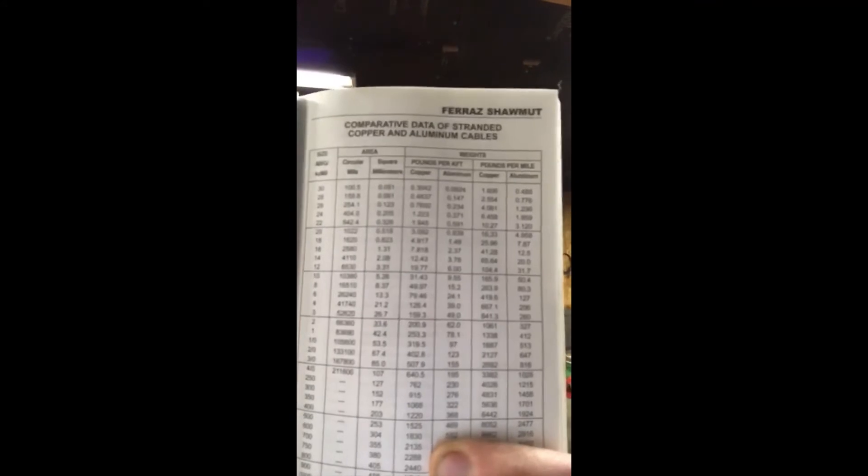If you wanted to do the math — which we're not going to go into — this is a Ferraz Shawmut book that calculates wire diameter, gauge size, and length of wire that you can put on a circuit. You're going to see in the pictures that this electric heater runs 12 amps. My breaker was 20 amps and my wire gauge size was 16. That particular gauge at that length is only rated for 10 amps.